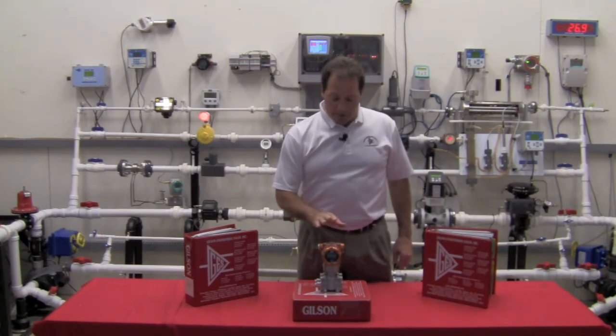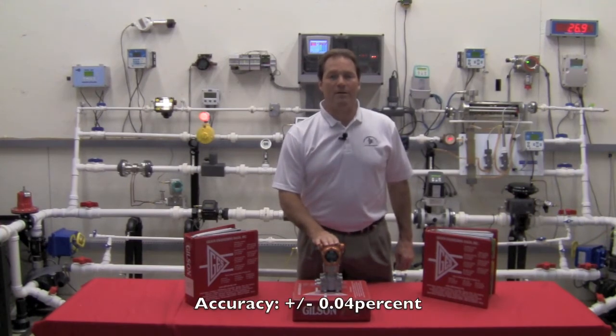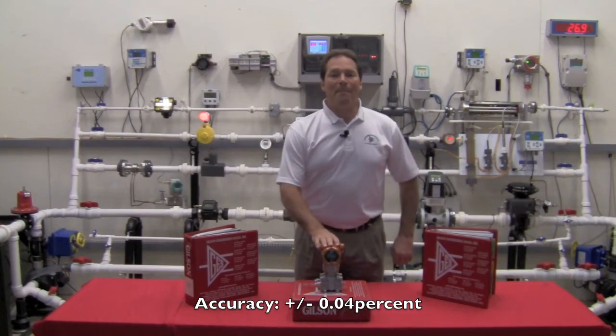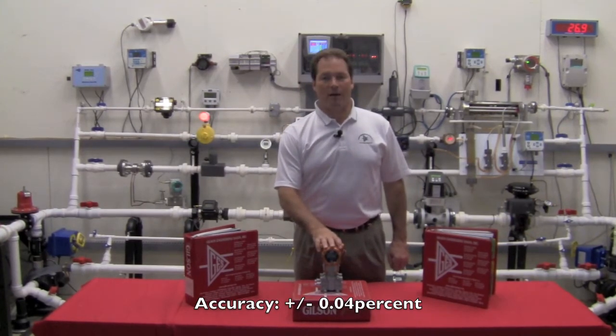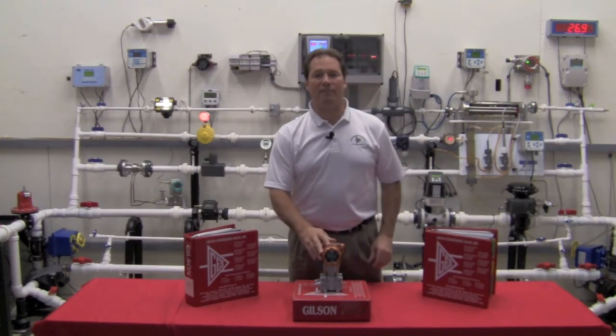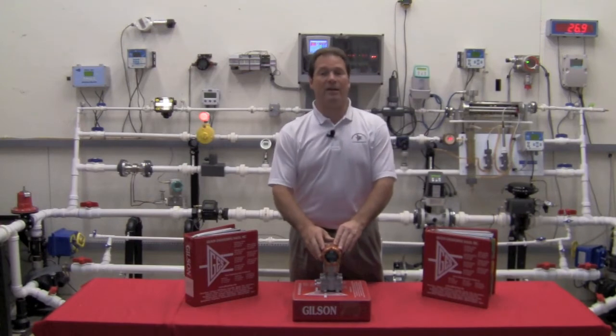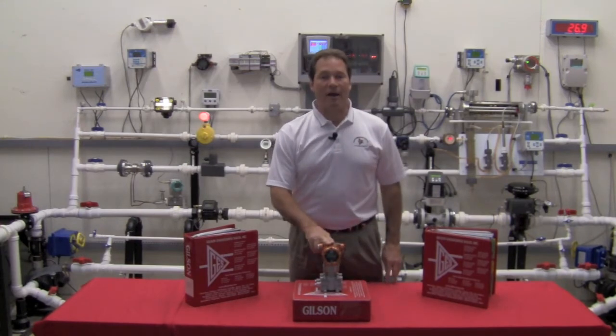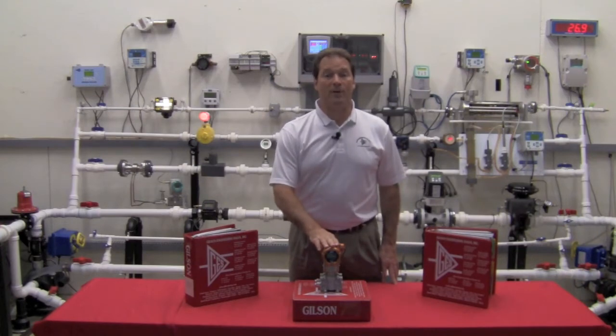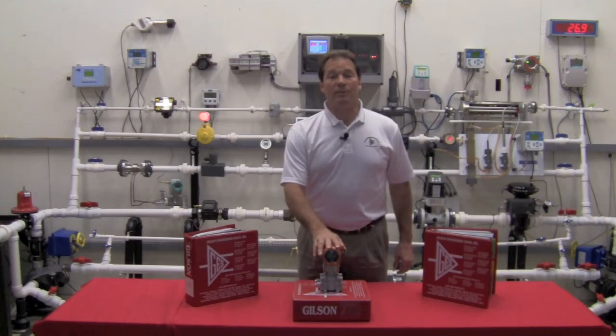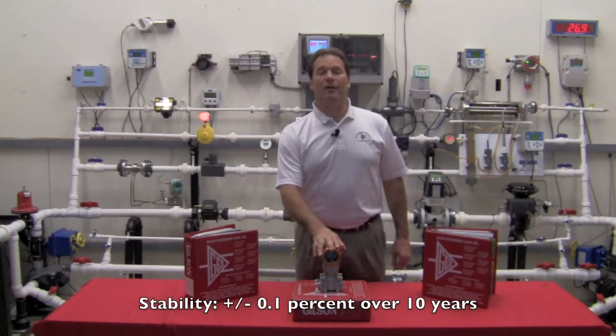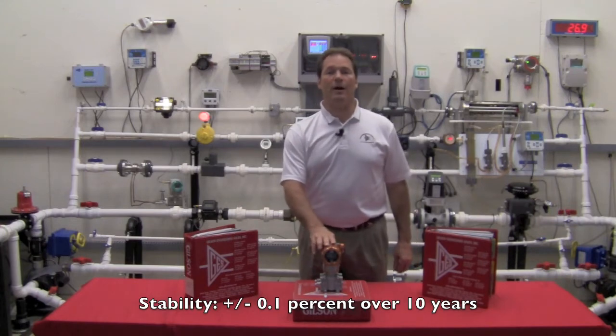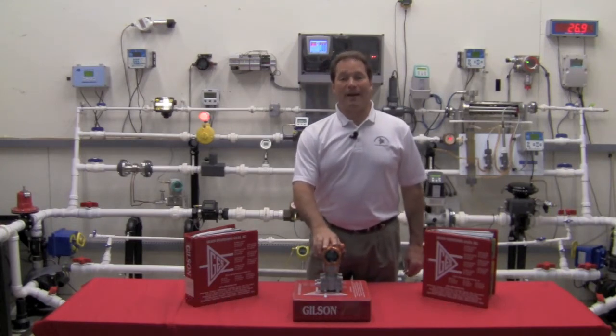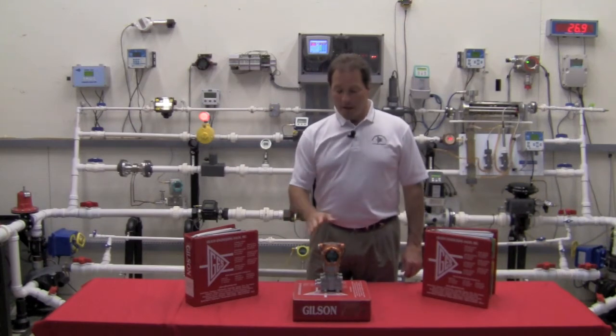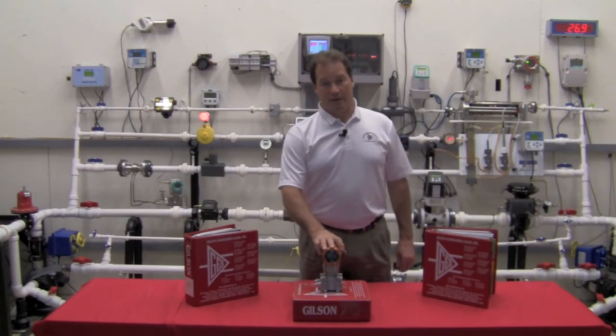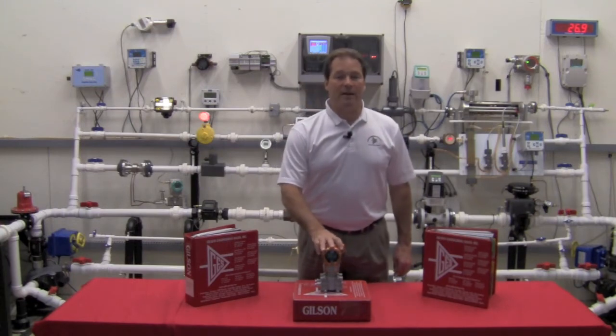Number one, the transmitter accuracy is plus or minus 0.04%. That matches the high-end accuracy of most other product lines. They'll offer you a plus or minus 0.75% accuracy transmitter and then charge you a ridiculous fee, maybe $1,000, to match the accuracy of the standard Yamatake 0.04% accurate unit. We have a long-term stability of plus or minus 0.1% over a 10-year period. That's 0.1% of the URL. Think of how much money you can save on your maintenance plans if you back off on how often you check your calibrations. This unit's guaranteed no more than 0.1% over a 10-year period. That's the best in the industry.